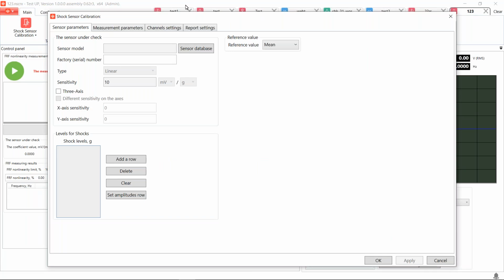The procedure of shock sensor calibration is applied when the amplitude characteristics of the sensor are to be determined. And as Alina said, ISO 16063-22 is the main standard for the shock calibration procedure. The process of shock sensor calibration can be divided into two parts. First, we need to perform a series of high amplitude shocks. And second, we need to compare the results with the reference accelerometer data.